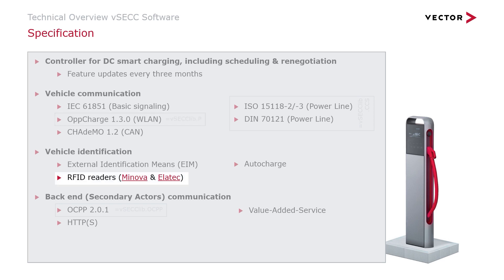The authorization of a charging process can be done with various methods, one of which is an RFID reader. The vSECC now supports authorizing a transaction using RFID tokens. At this moment, two RFID readers are supported by the vSECC Controllers: the MCRN2 of Minova and the TWN4 Multitec of Elatec. Both readers support RS-232, and you only need one reader for two connectors.